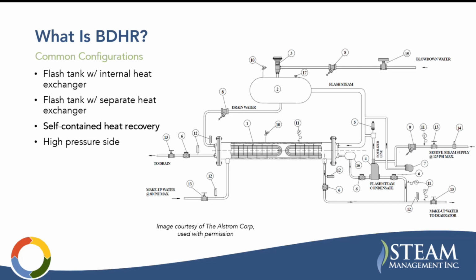That's another example. And then this last one, this image is provided by Alstrom, is one of their self-contained heat recovery units. This is an interesting design. It kind of uses the flash steam within the unit. So the blowdown comes in, it flashes off in this flash tank. The drain goes into one tube bundle and heats the makeup water, and the steam goes into a second tube bundle to further heat the makeup water.